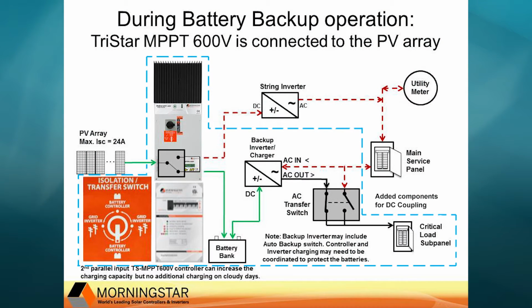And so now when the grid goes out, what happens? So when the grid goes out, your critical loads panel, which has been constantly charged by the inverter charger down from the grid-tied inverter during grid-tied operation, will transfer the power seamlessly to pick up your loads. So there should be no lag in time operation there, no lights going off. Your clock on your microwave should continue to read the same time. So then when that happens, you're running off of battery power, and your inverter charger is taking that DC battery power and transitioning it to AC to power those critical loads. In the same way as a generator and an automatic transfer switch solution would work, we envision this being very similar. It also eliminates the need for a 5-minute interval for reconnect on AC coupled systems. It's a continuous flow of power. Charging is backed up whenever the sun is shining, and that load transfer time can be made to be a seamless transition during an outage.